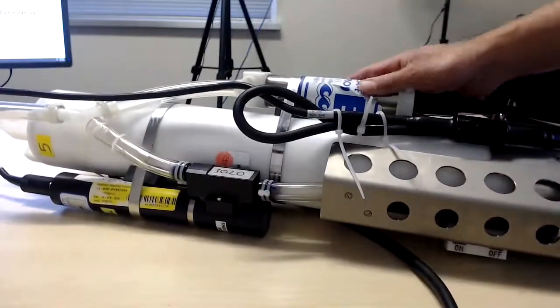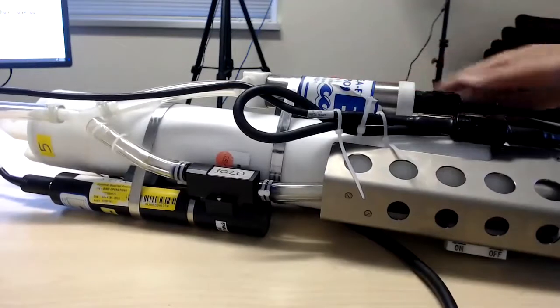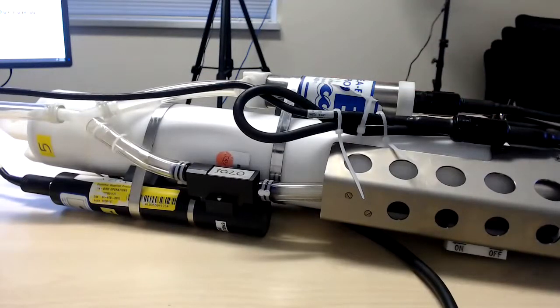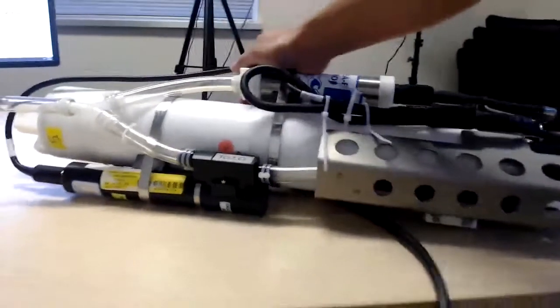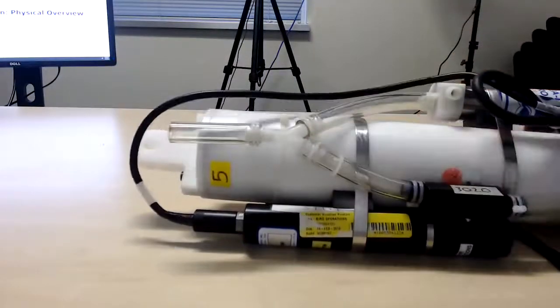It's important that this pump is pulling water and not pushing water, because if it were pushing water and it preceded all the sensors, then the pump would be affecting the sample. However, it's pulling water, so that's not a problem. And so we get really tight alignment between our temperature sensor, our conductivity sensor, our oxygen sensor, and anything else we might have plumbed in there. Now you might also notice we have this little Y fitting right here on the plumbing.